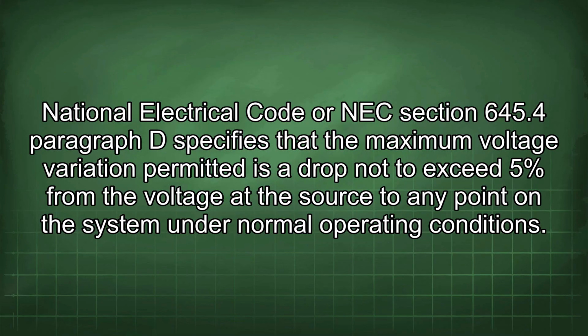National Electrical Code or NEC Section 645.4 paragraph D specifies that the maximum voltage variation permitted is a drop not to exceed 5% from the voltage at the source to any point on the system under normal operating conditions.